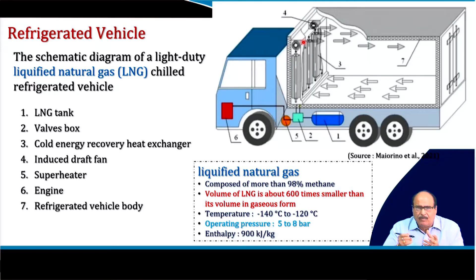Properties of liquefied natural gas include: it is composed of more than 98% methane. The volume of LNG is about 600 times smaller than its volume in gaseous form. Its temperature is generally minus 140 to minus 120 degrees Celsius. Operating pressure is 5 to 8 bar and enthalpy is 900 kilojoules per kg.